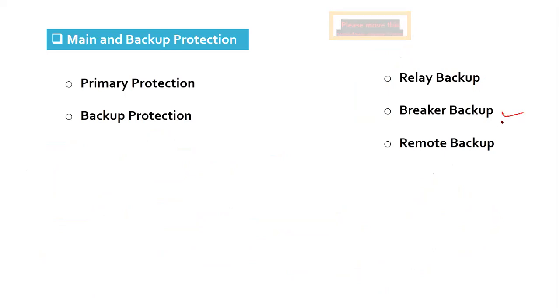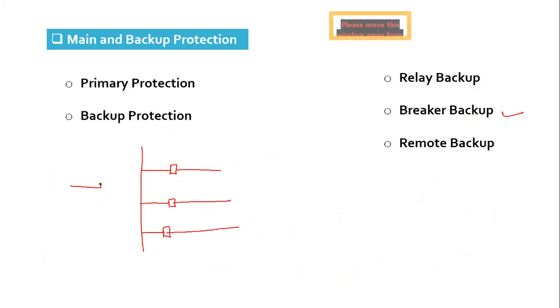Second is breaker backup. What is breaker backup? Suppose here we have 3 outgoing and 2 incoming lines in a substation, and suppose there is a fault somewhere in the other part of the system.